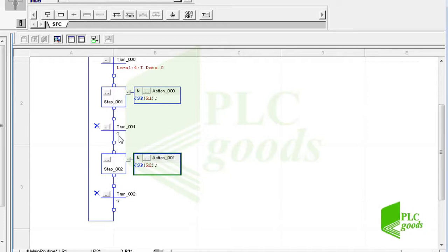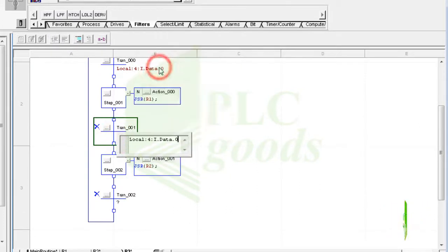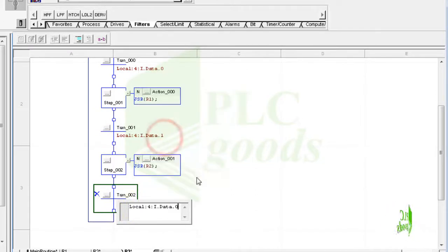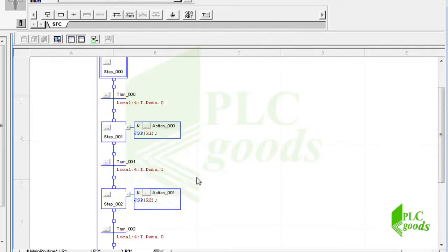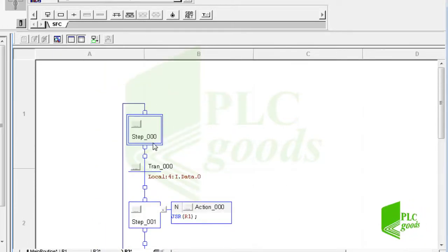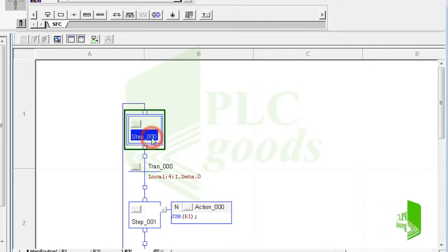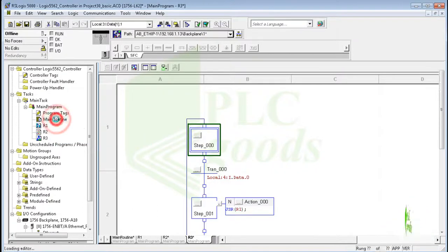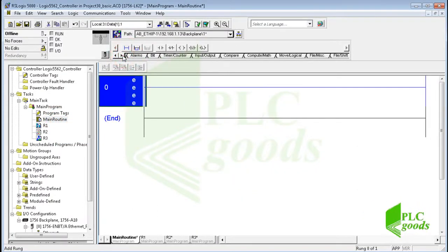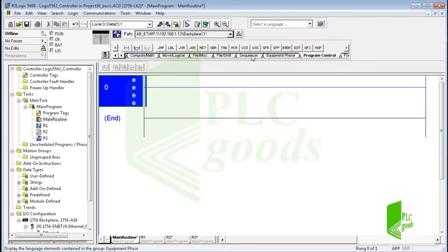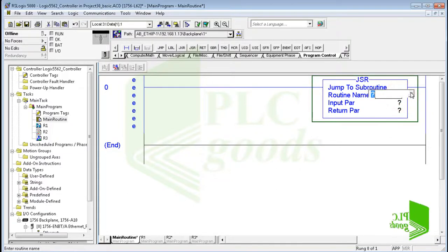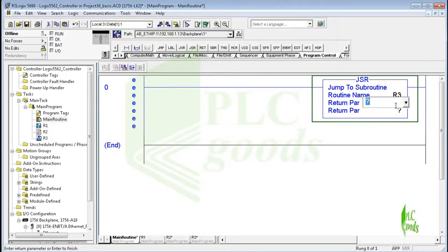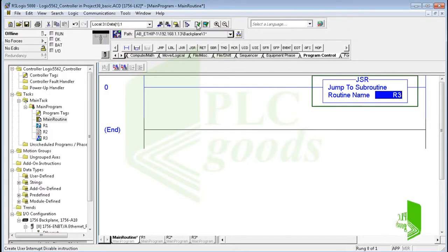Let me use the second and third digital inputs as the transition conditions respectively for the second and third steps. This is a simple program in SFC language with three steps and three transition conditions. It will be repeated because I connect the last transition to the first step. This program has been written inside routine R3, so let me call that from the main routine. Now let me download and test my program.